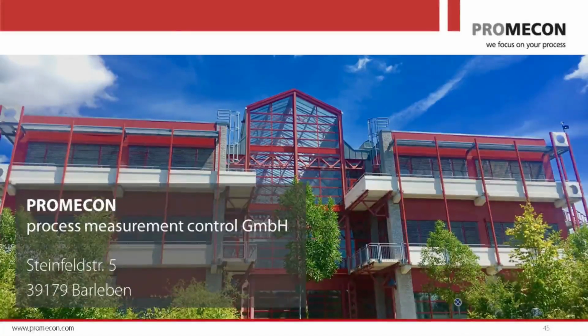Okay, quite a bit there. What is the maintenance interval for performing maintenance on your system, and what does this maintenance involve? Yeah, the problem is that many of our clients don't do any maintenance anymore. So they come back to us after 10 years and say, "Wow, one sensor is not working." Well, then the sensor is either burnt or broken, or the cable is ripped or something.